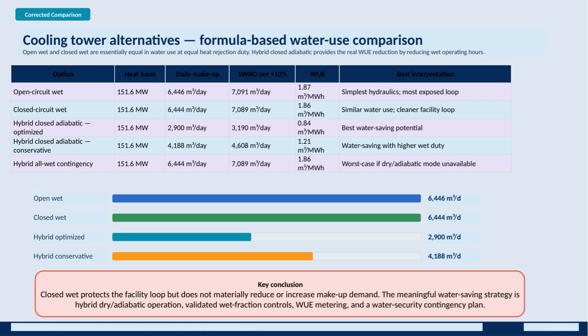However, if dry or adiabatic modes are unavailable and the system operates fully wet on contingency, water use jumps back up to levels similar to traditional wet cooling towers. To summarize the key takeaway, while closed wet towers protect the system loop, they don't drastically change water consumption. The meaningful reductions are achieved through hybrid dry/adiabatic cooling, carefully controlled wet operation, regular WUE measurement, and having a water security contingency plan ready. This integrated approach is essential for sustainable water management in high-demand cooling applications like the Badham Coastal Data Center.